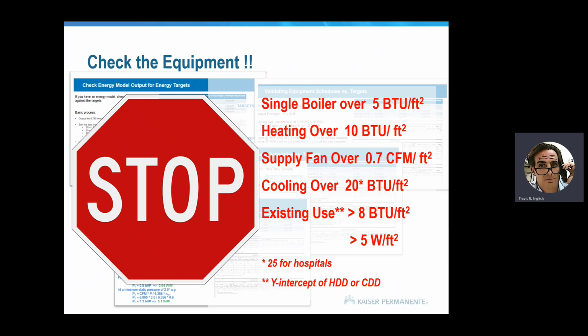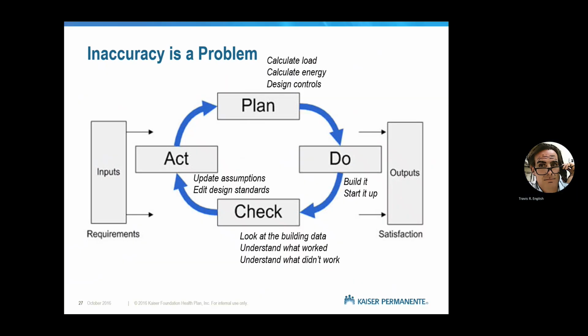If you're thinking of installing air handlers that are bigger than 0.7 CFM per square foot, then stop. You've clearly done something incorrectly with your load calculations. We need to talk about that. If you're thinking about installing cooling that's larger than 20 BTU a square foot, then just stop, right? There's something off about your load calcs, and we need to talk about that. And we know that those systems are not actually going to make it when it comes to turning down and doing things appropriately.